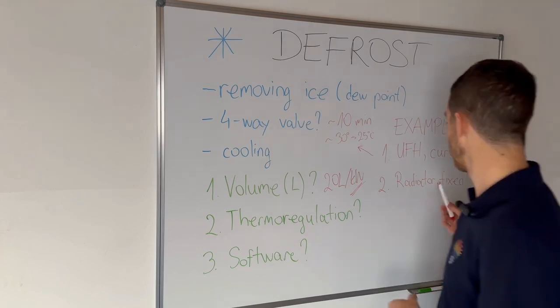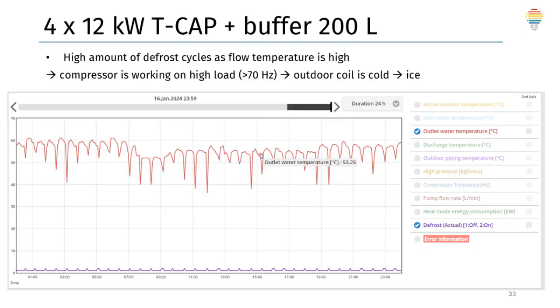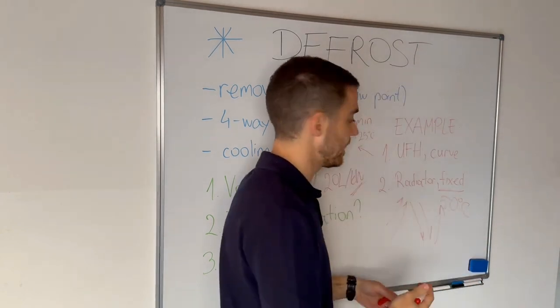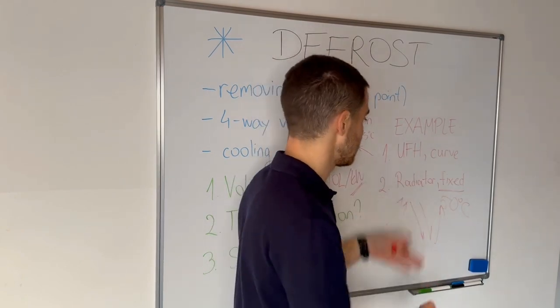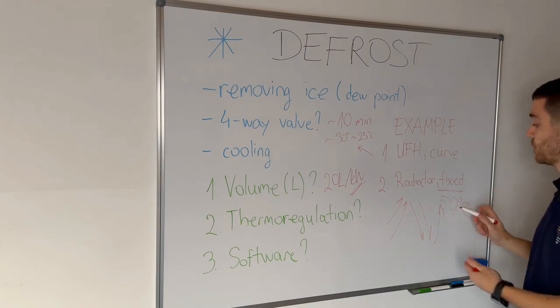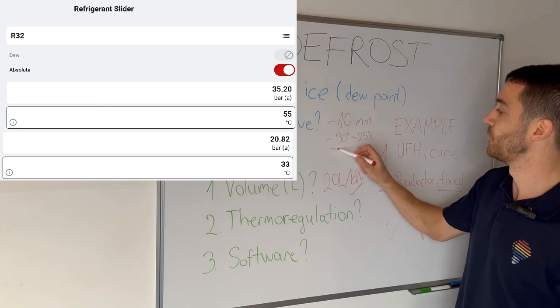Another example is a radiator system — the problem is not that it's a radiator, but that it's on a fixed flow temperature: always 50 degrees. This system has defrost cycles very frequently. Why? Because the compressor runs high, the fan runs high, then we have ice, then a turn-off, and on again — fast compressor and fan movement, and fast ice build-up. Defrost cycles are more frequent because we're doing on and off with a really high temperature. For that temperature you need, for example, 35 bar of R32, whereas at lower conditions you need probably 21 bar.